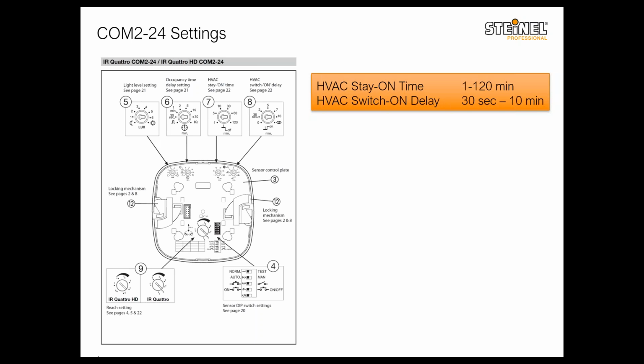And then, as you can see in the image here, a COM2 sensor will give us an isolated normally open or normally closed relay to integrate with some other system or to be used as a signaling relay for another power pack or another contactor. As you can see on the back of the sensor, on the COM1 we have the two dials on the top left, but on the COM2 we have the additional dial number 7 and dial number 8. Dial number 7 is the stay on time of that relay, and dial number 8 is the switch on delay.